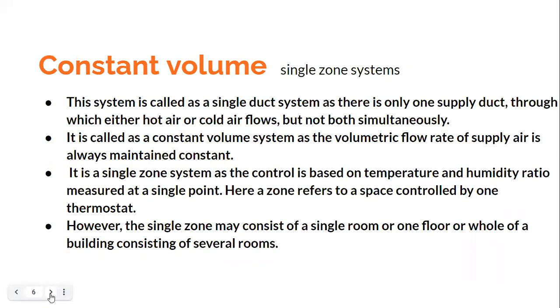Now, let us just focus on what exactly this constant volume single zone system is. As I said, this system is called a single duct system for the simple reason that there is only a single supply duct. In the supply duct, either you supply the hot air or the cold air, but not simultaneously. It is also a constant volume system because you maintain the flow rate of the supply air constant. So if you want to cool a particular zone, you are going to supply a constant volume of supply air always.